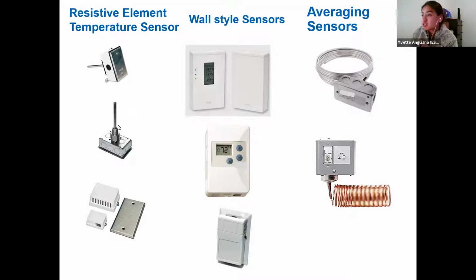You've got an immersion type temperature sensor, which you would put into a piping system, and it's measuring the temperature of whatever media may be in there, whether it's water, glycol, or another media. You've got a typical room temperature sensor where the air is flowing through this device, touching a bulb in that device and then going back to your BMS system. And then you also have wall style sensors. As you can see here, we've got ones with digital displays, without digital displays. It all depends on what your client is asking for.